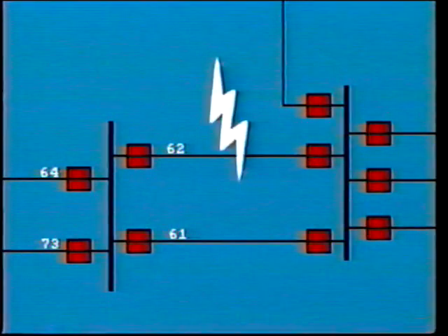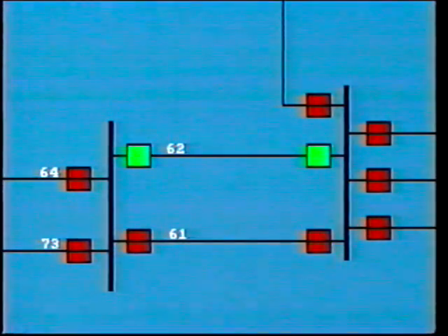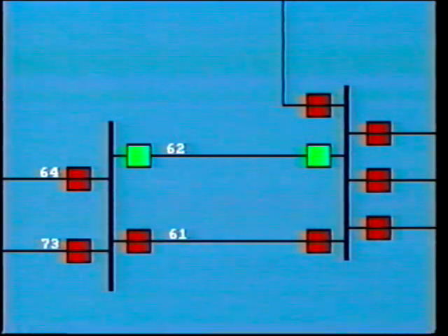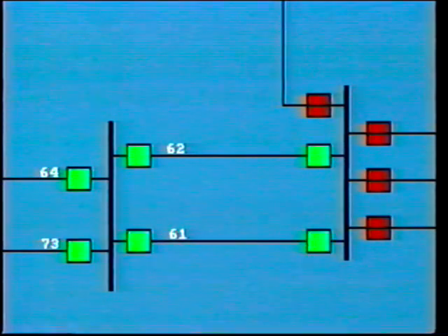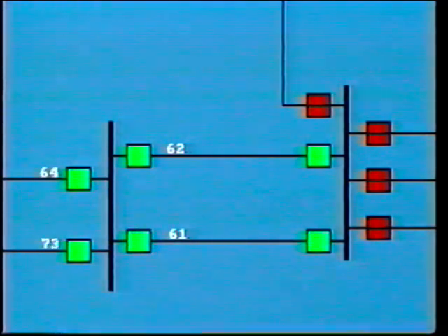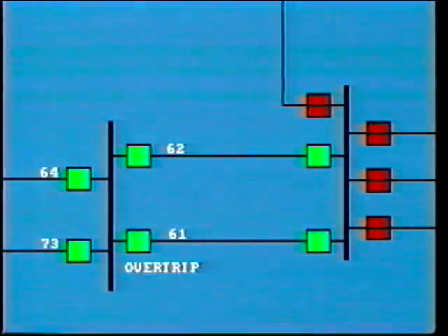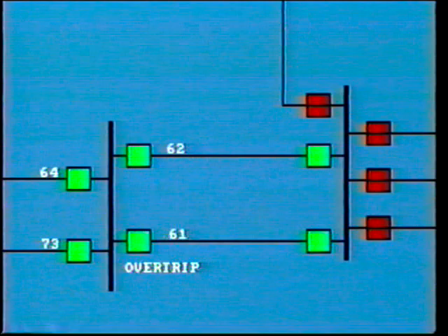Sure enough, there goes line 62, tripped at each end by ground protection. But look, line 61 has tripped, and lines 64 and 73 have tripped as far back as the generator substation. Apparently, some misoperation in the protection equipment has caused overtrip, with the consequent interruption in service to customers.